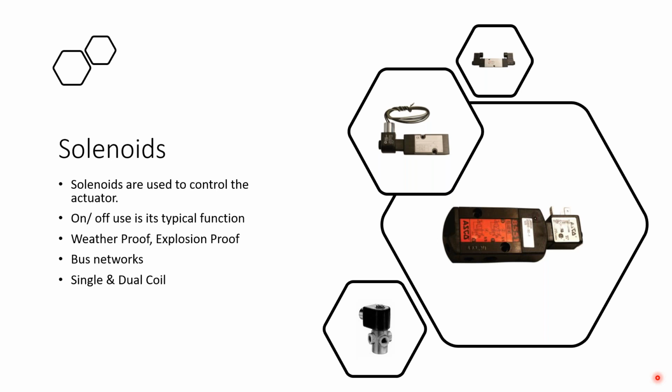But if you have a signal coming, let's say, from a controller of sorts, you don't necessarily have to have a solenoid. Now, a lot of companies will use a traditional three-way, two-position solenoid, where they'll have supply coming in, and this is energized all the time. In an upset condition, this allows it to close and vent, and it puts the valve into the fail position. So there's a number of things to do, but I don't think you necessarily have to have a solenoid to make an actuator open and close, no.